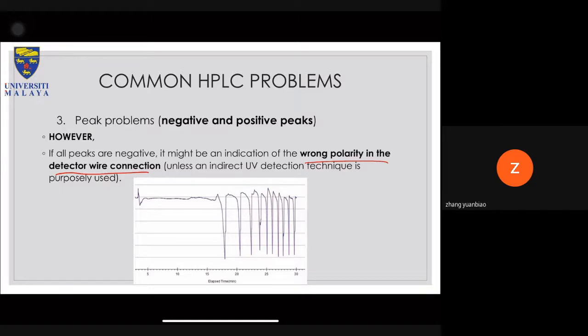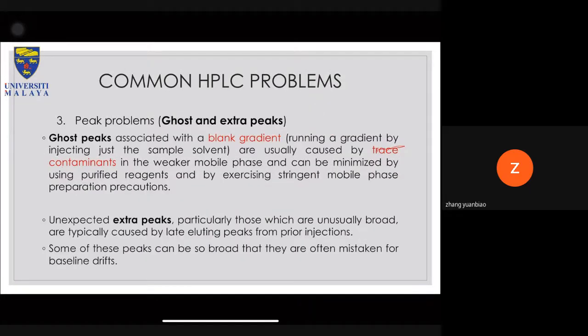Ghosts and extra peaks. Ghost peaks are associated with blank gradient, meaning that when you are running your blank, you actually see a peak coming out. These are usually caused by a trace contaminant in the weaker mobile phase and can be minimized by using a purified reagent or by exercising stringent mobile phase preparation precautions. You might also see a ghost peak from the column. I didn't put it here, but it might also come from the column, whereby when you do run number one, for example, you had something that is stuck to the column for a very, very long time. So you need to wash it multiple times to clear out this ghost peak.